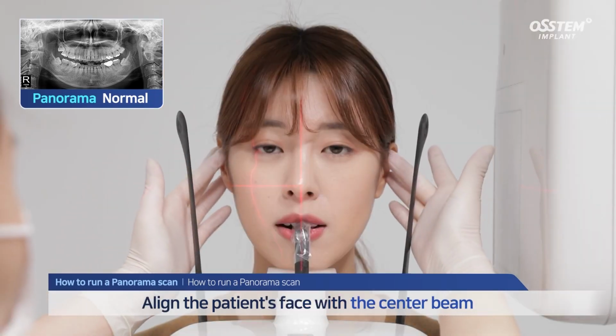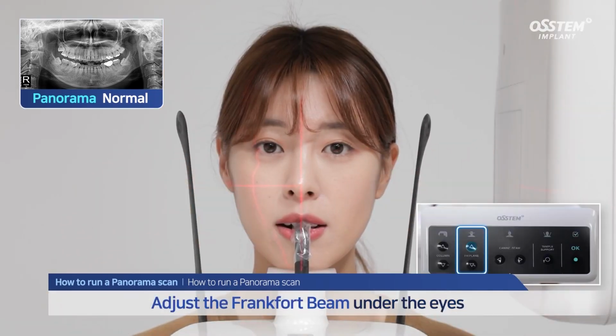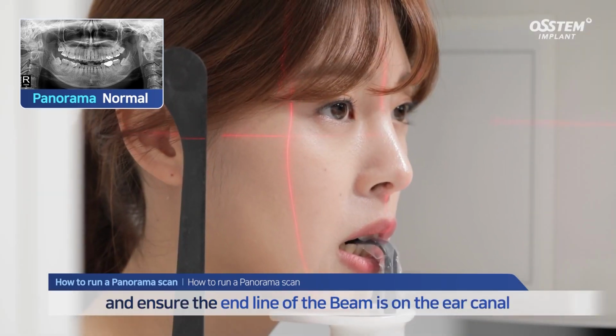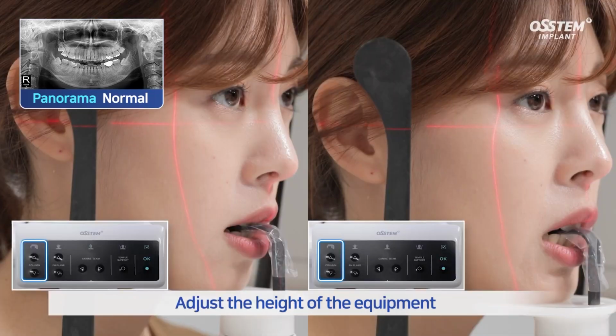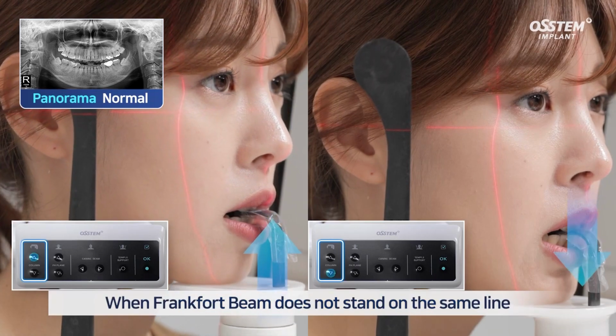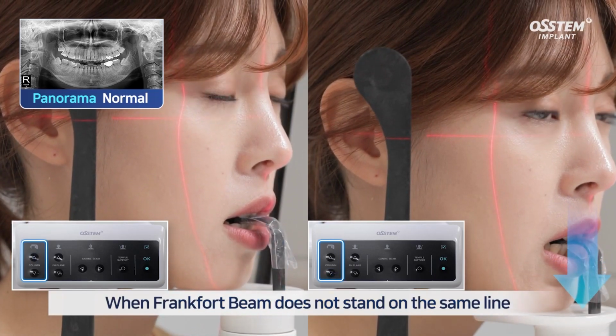Align the patient's face with the center beam. Adjust the Frankfort beam under the eyes and ensure that the end line of the beam stands on the ear canal. If the Frankfort beam is not on the same line, press the column up or down buttons to adjust.